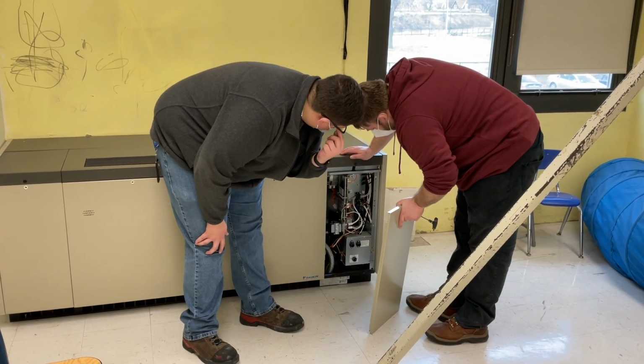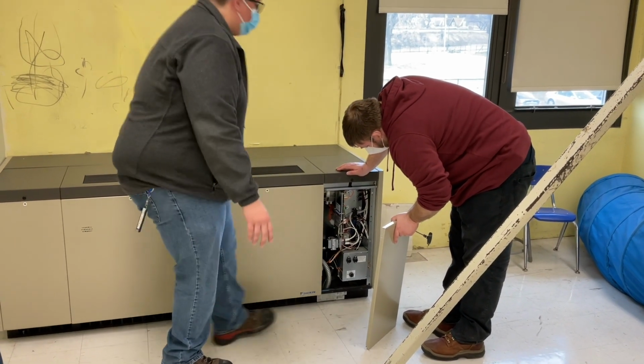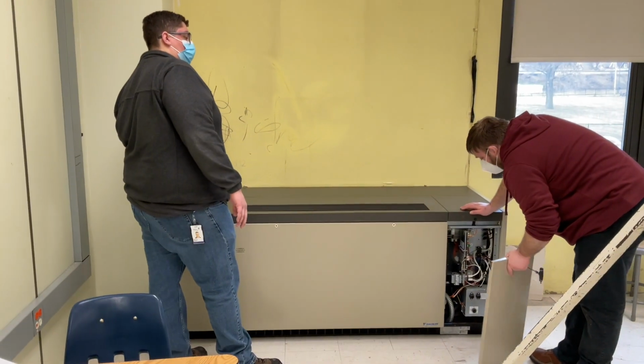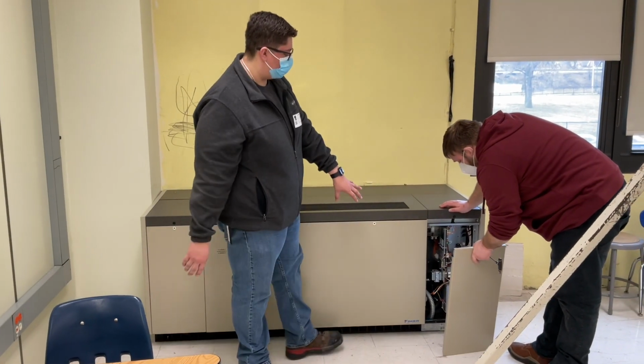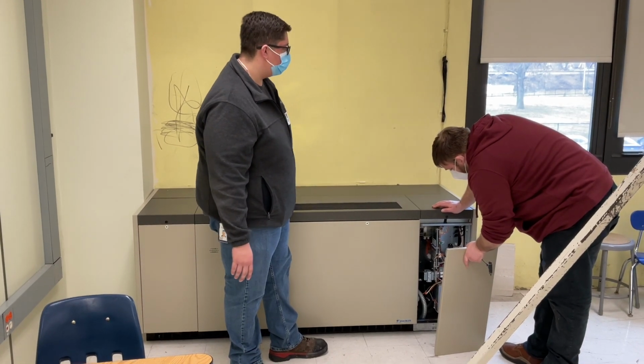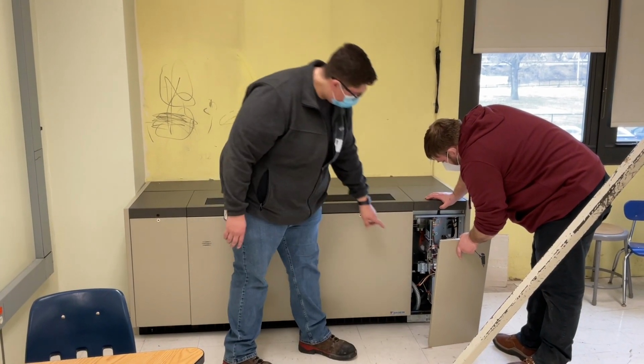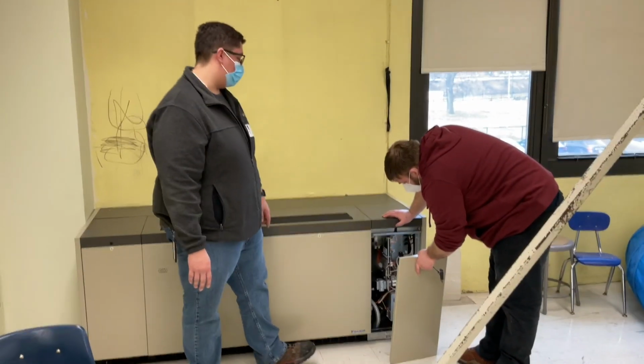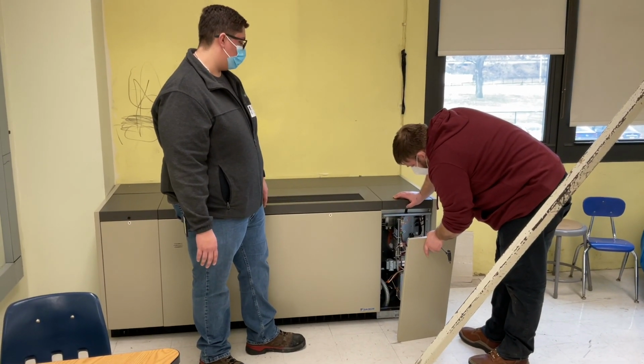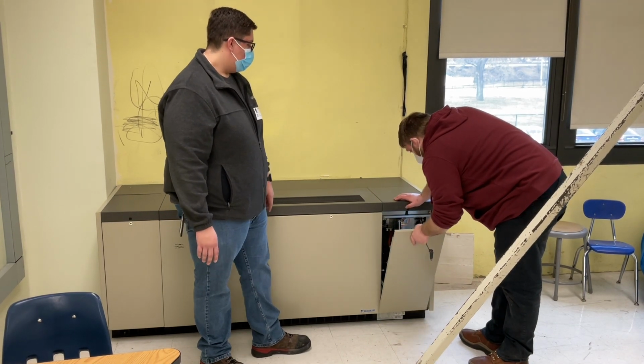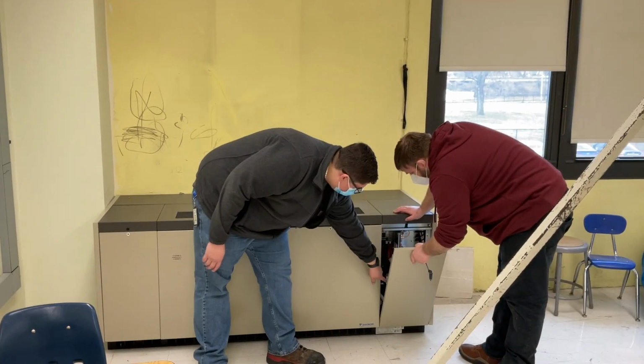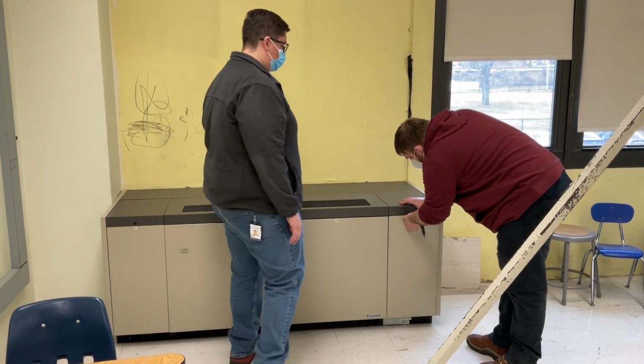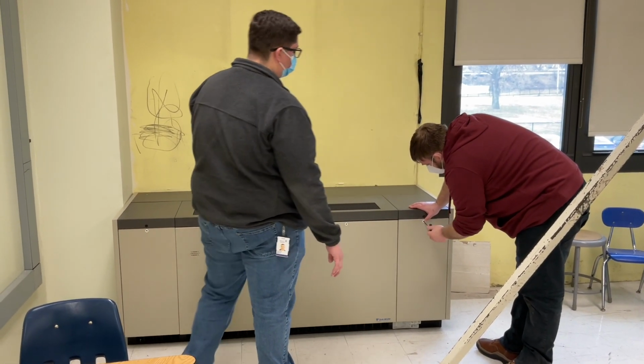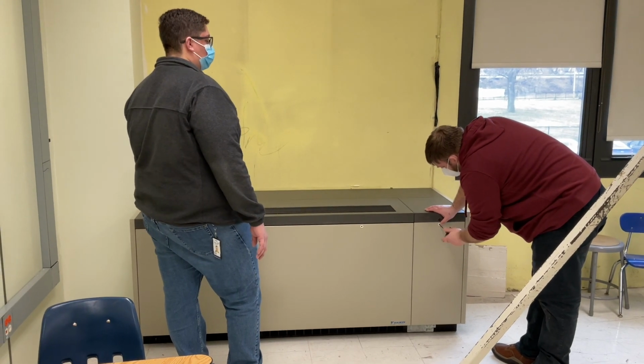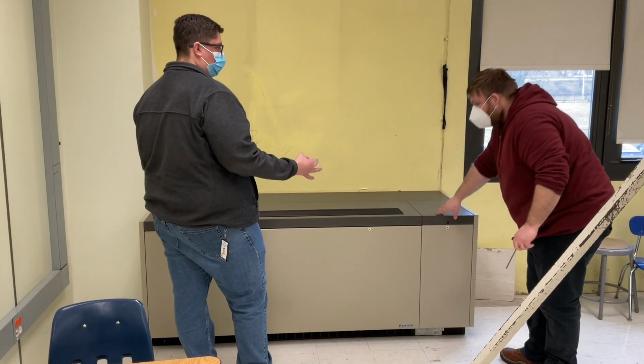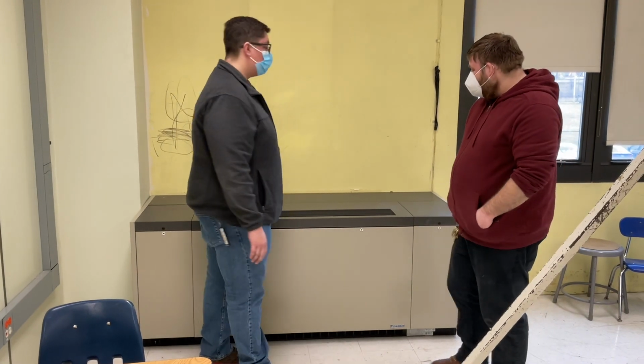So that's a question you might have to ask Daikin about, like the heating not coming on. Because all we're doing is closing the contacts there, and it goes back to their control. And then they determine, I believe there's a high limit in there and all that to stop it from going. Also the speed selector switch, CPS, the engineer requested that they're all at medium. That's just how they want it. And then fan status is inside this box. That's how we're reading fan status. So if you ever have one that possibly goes bad, that would be the first place to check. There's a little current donut in there. That's pretty much it.